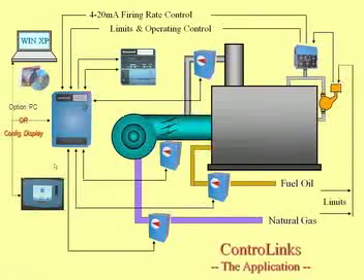We find, though, more often the benefit to the display is that it allows a lot more interaction with the controller. Many people like to have that left there all the time. That talks down to the controller. It's kind of the brains of the system, if you will, and it operates our actuators. In this picture, for example, flue gas recirculation, one for forced draft or combustion air, one for our natural gas and fuel oil. It interacts with your existing flame safeguard.